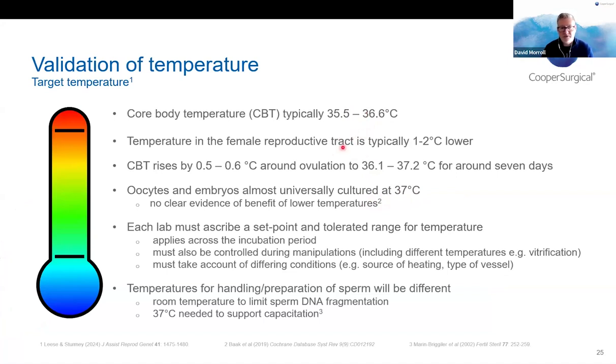And temperatures within the female reproductive tract are even lower, typically 1 to 2 degrees, although that is dependent on the time in the menstrual cycle, because as you're probably aware, around the time of ovulation, the core body temperature actually rises. The key point here is that we're likely to be setting at 37 degrees, but it's up to individual labs to ascribe a set point and the tolerated range for temperatures, depending on what they're doing, of course.